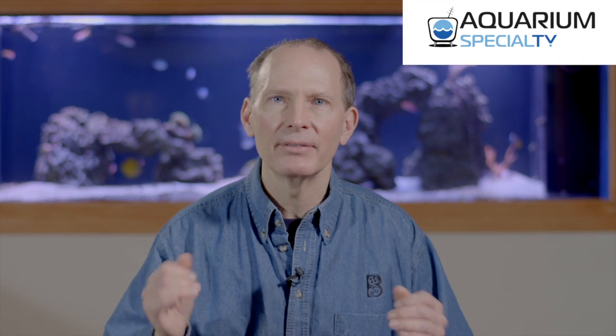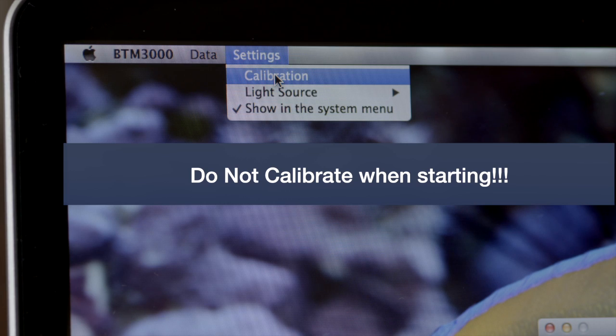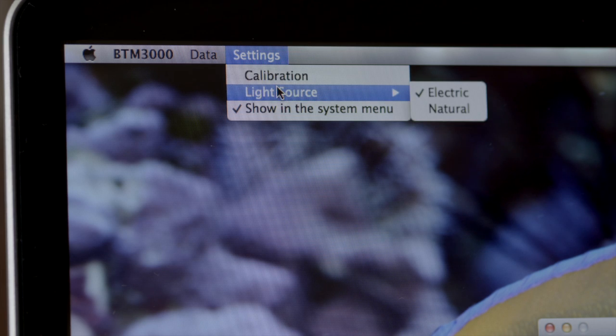It is not advisable to calibrate your PAR sensor initially, as your BTM3000 is calibrated right when it leaves the factory. The options listed are electric or natural, depending upon whether your tank uses natural sunlight or artificial electric light. Most tanks will have electric light, so this is set as the factory default.